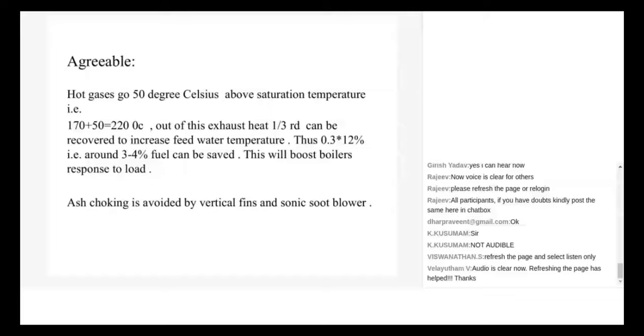If I keep it off, then the pressure starts dropping, so I am running the ID fan as it is. I don't have any means of controlling it, and that is how this whole system is running. Secondly, if you make a mistake that you give some theoretically designed economizer to recover that heat, then ash choking—if there are horizontal fins, it will definitely choke. So you have to give vertical fins, and on top of it you have to give a sonic soot blower also for making sure it is sustainable.